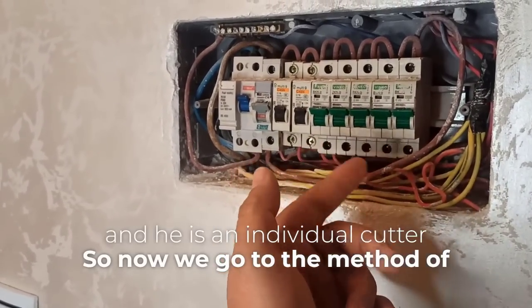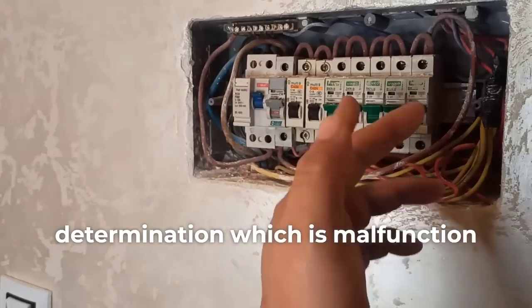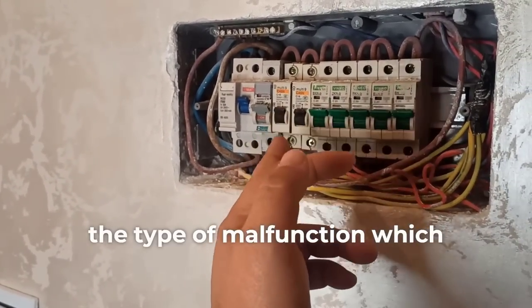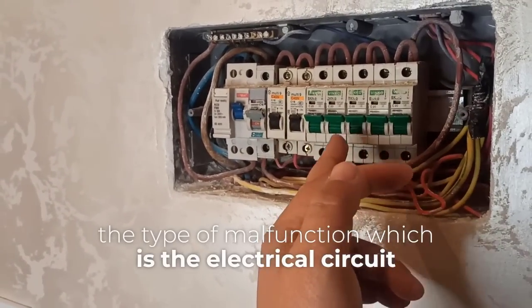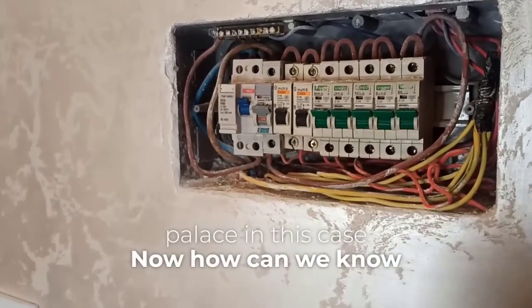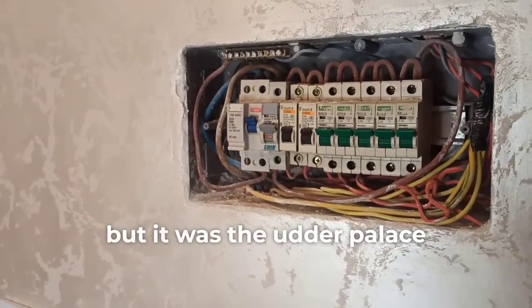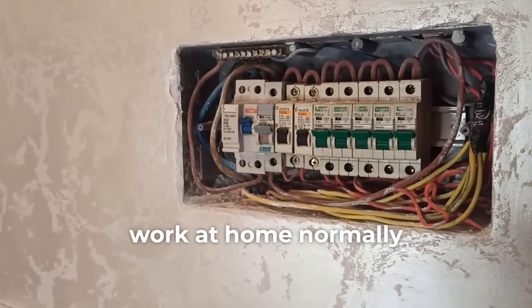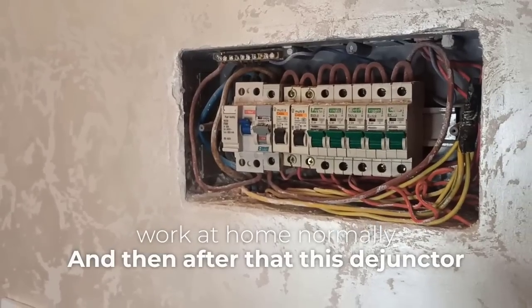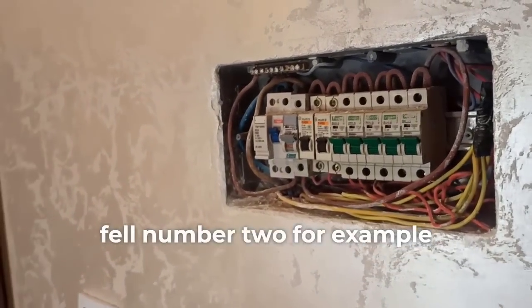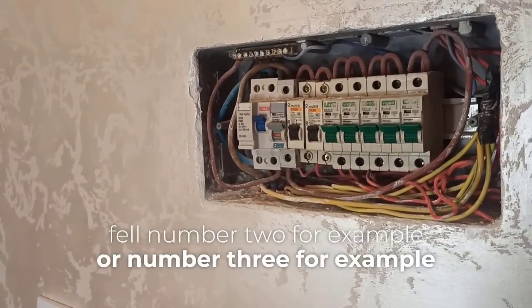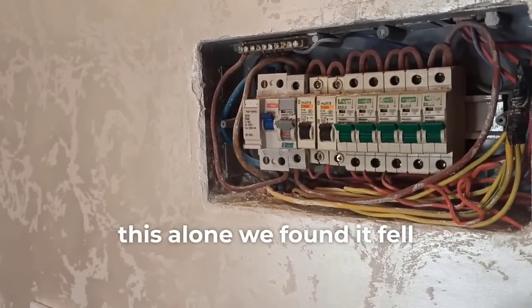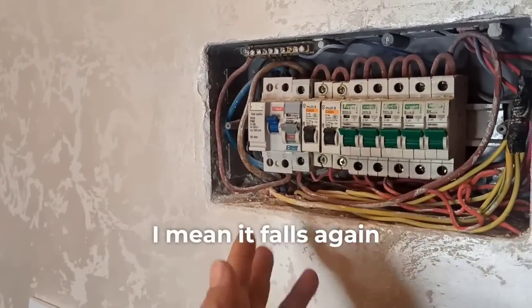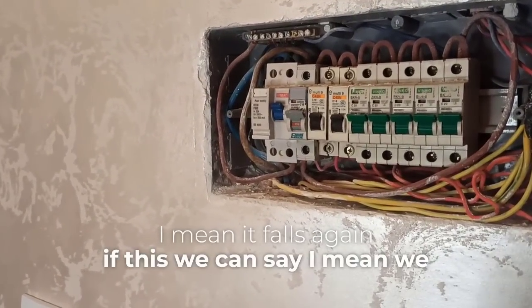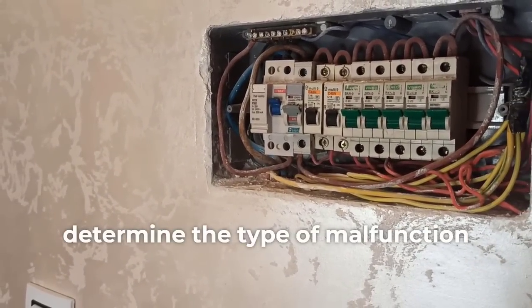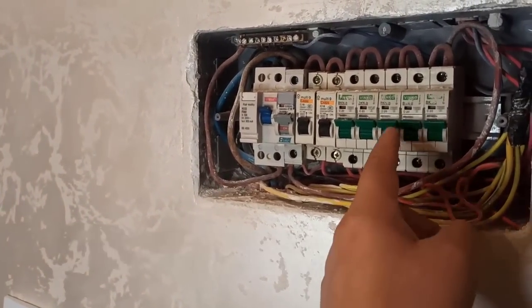So now we go to the method of determination for malfunction 2, the type of malfunction which is the short circuit in this case. Now, how can we know? When the electricity works at home normally, and then after that, this breaker number 2, for example, or number 3, trips on its own. We found it tripped alone, and when we go back, I mean, it trips again. If this happens, we can say we determine the type of malfunction, which is a short circuit in the electrical circuit.